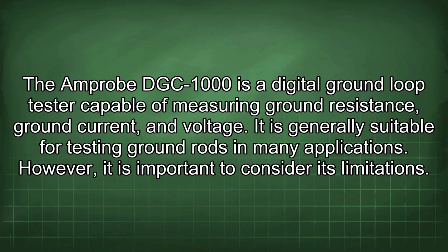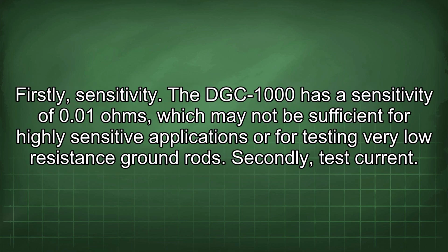The Amprobe DGC-1000 is a digital ground loop tester capable of measuring ground resistance, ground current, and voltage. It is generally suitable for testing ground rods in many applications. However, it is important to consider its limitations. Firstly, sensitivity. The DGC-1000 has a sensitivity of 0.01 ohms, which may not be sufficient for highly sensitive applications or for testing very low resistance ground rods.